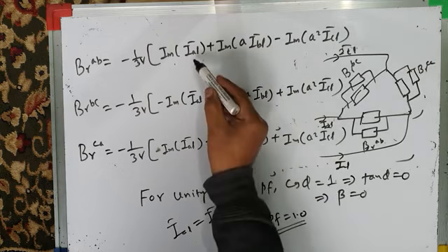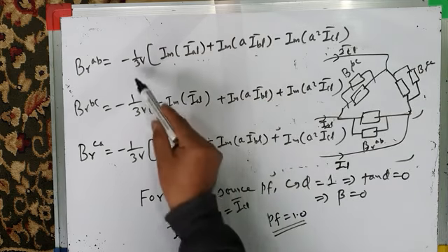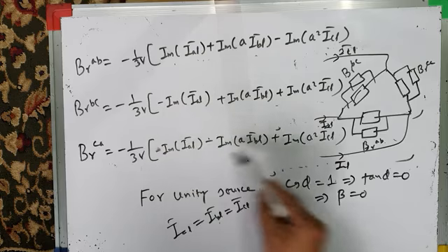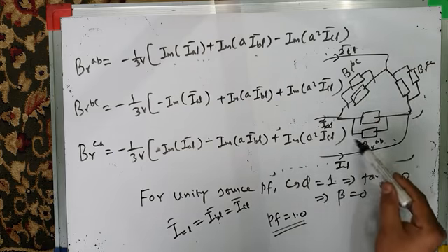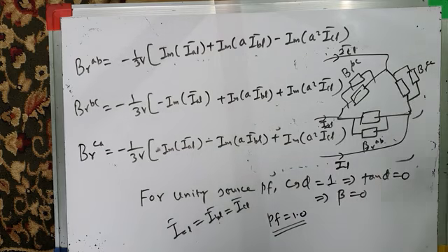So therefore, if you know the load currents of this unbalanced three-phase delta connected load, IAL, IBL, ICL, and you know the source voltage, the source is balanced, substitute these load currents in these equations and you will get the susceptances of all three branches. Connect these compensators of the given susceptances which you have calculated by these equations, and your load balancing as well as reactive power compensation will be done. More on it in the next lecture, inshallah. In the next lecture we will do more analysis of this load balancing using a passive solution.